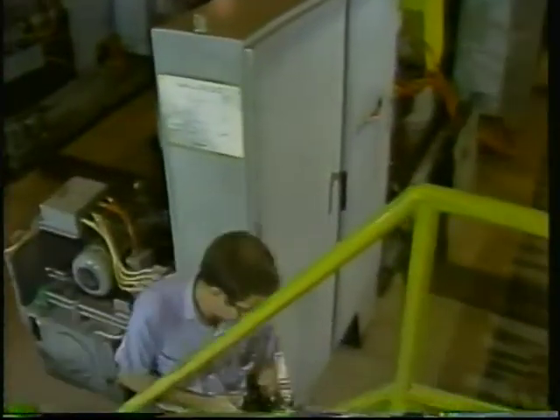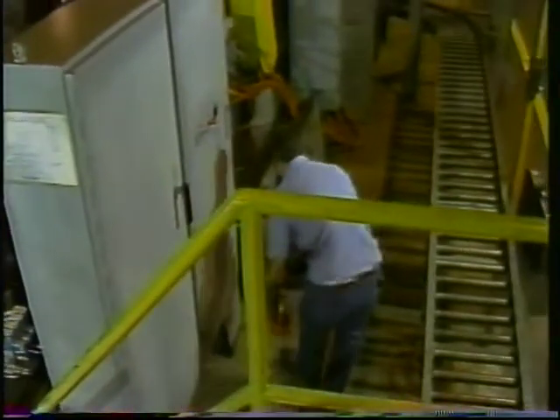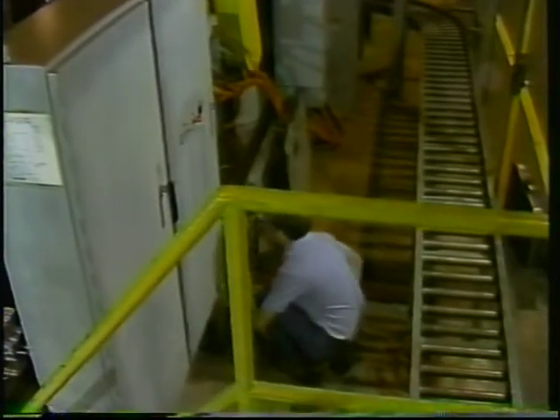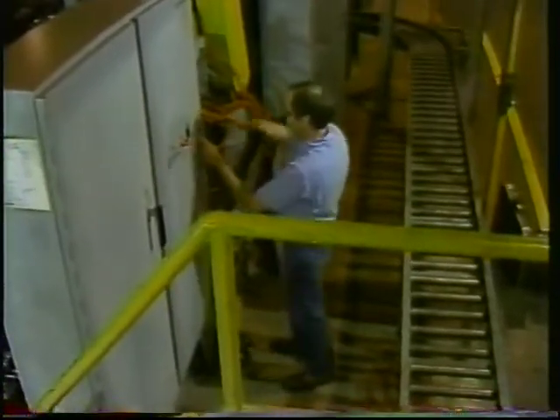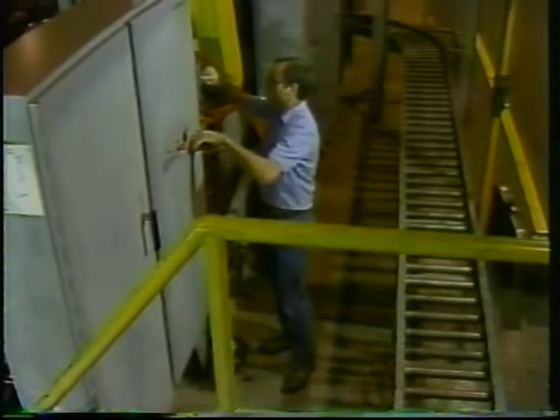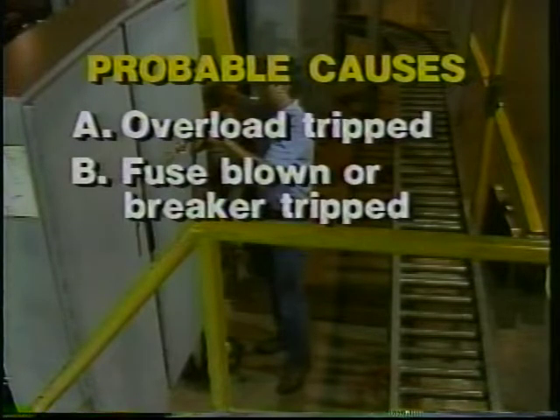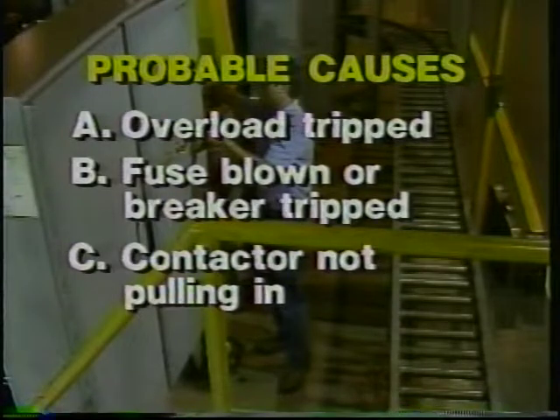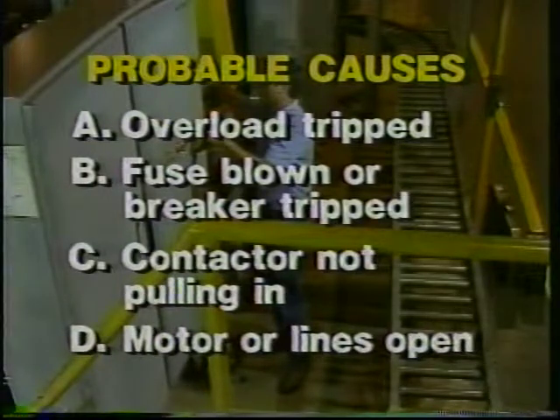Usually, when you are called out to work on a motor, it is because for some reason the motor will not run. It's pretty obvious that power must not be getting through the motor. And anyone who has any experience with motors would know that chances are an overload is tripped, a main fuse has blown, or a circuit breaker has tripped, or the contactor to the motor is not pulling in. It is also possible that there is an open in the motor itself or the lines to it. Let's suppose that the problem is an open in the motor. The motor windings have burned out, in other words.